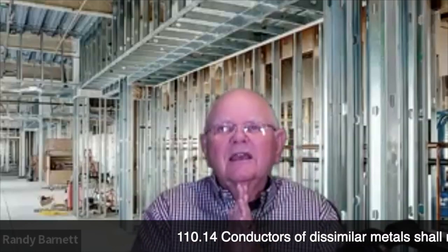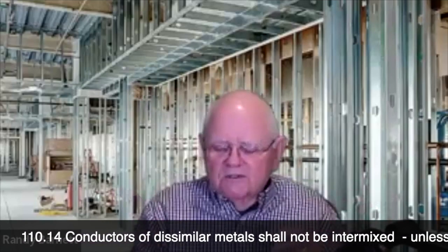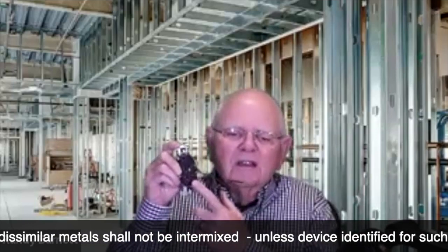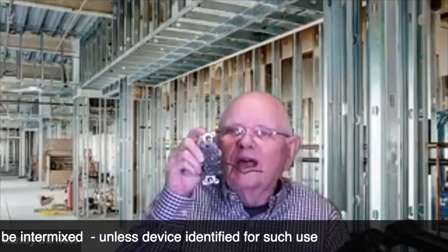So we want to make sure that if we're going to put dissimilar metals together, that whatever it is we use says we can use it for dissimilar metals. For instance, on the back of this receptacle, which of course you can't see all that fine black print on the black plastic, huh? But anyway, it tells me Cu for copper, so I can use copper. Then it has Al, but there's a slash through the Al, meaning don't use aluminum. In fact, it also points out in 110.14, if you are using those little holes in there where you just push the number 14 and only number 14 in there to wire up these devices, then that can only be copper wire. We'd never want to try aluminum in these. But anyway, follow the instructions. Always follow manufacturer's instructions, right?